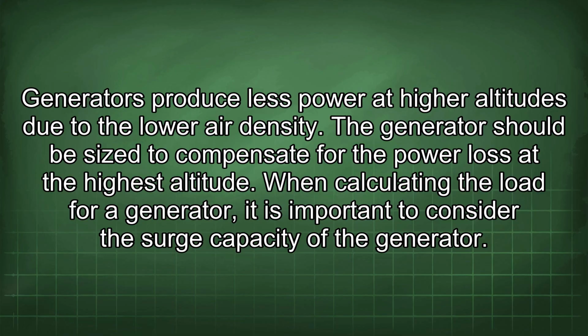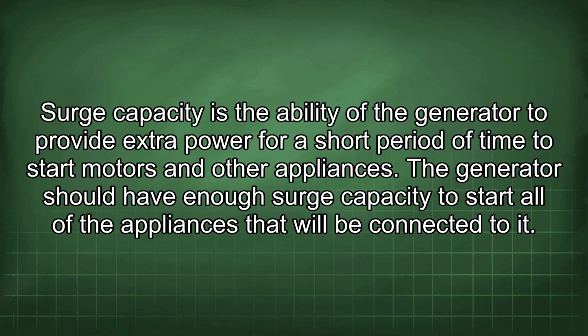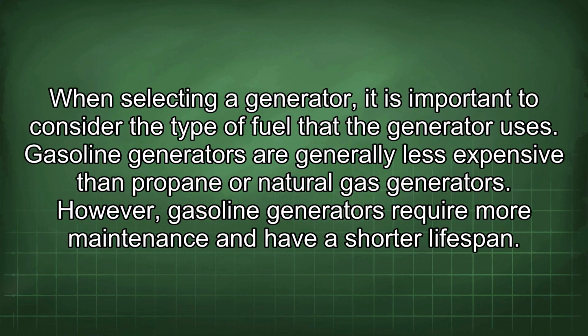When calculating the load for a generator, it is important to consider the surge capacity of the generator. Surge capacity is the ability of the generator to provide extra power for a short period of time to start motors and other appliances. The generator should have enough surge capacity to start all of the appliances that will be connected to it. When selecting a generator, it is important to consider the type of fuel that the generator uses.